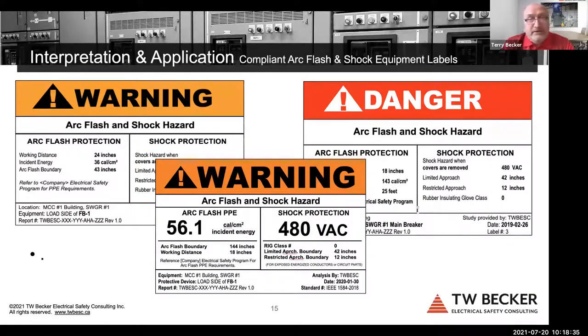And then, yes, some of the labels have HRC on it, and they shouldn't. The PPE shouldn't have HRC 2 on it. It should only be an arc thermal performance value that the worker's trained to look for. And then when the arc flash PPE category method is used, they know that arc flash PPE category 2 is min 8 calories, or arc flash PPE category 4 is min 40 calories. And here's a new technical change for you in Z462. We have an arc flash PPE category 5 now that's not in 70E, that's min 75 calories, but only if you use the arc flash PPE category method and only related to the low voltage switchgear electrical equipment row.